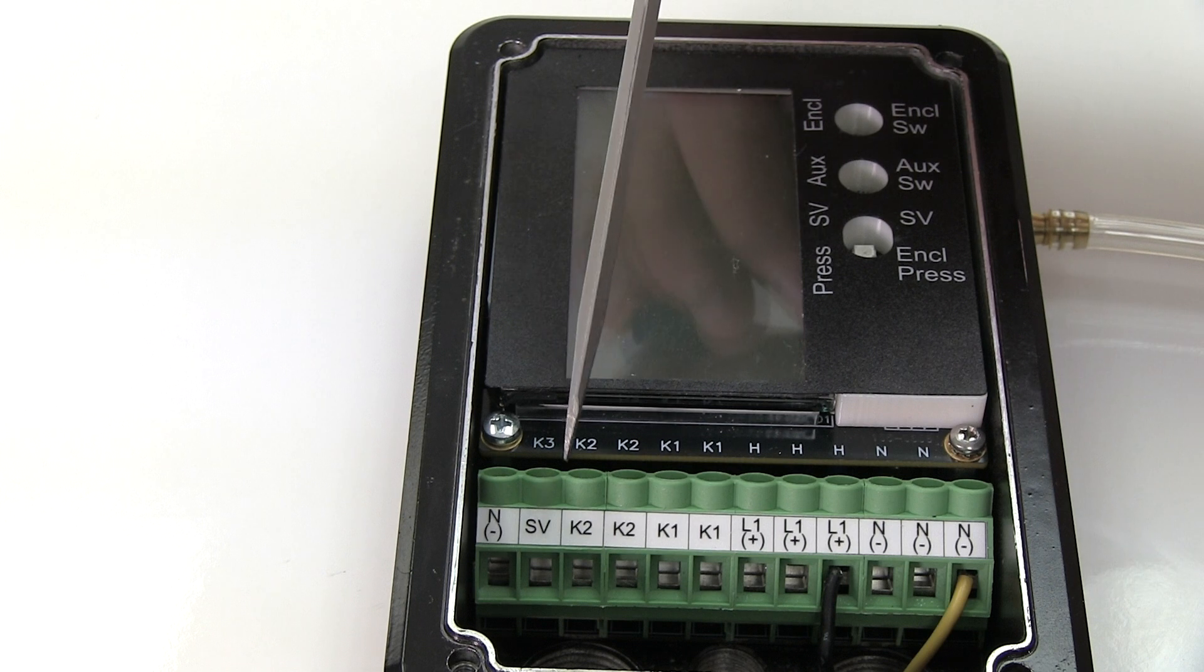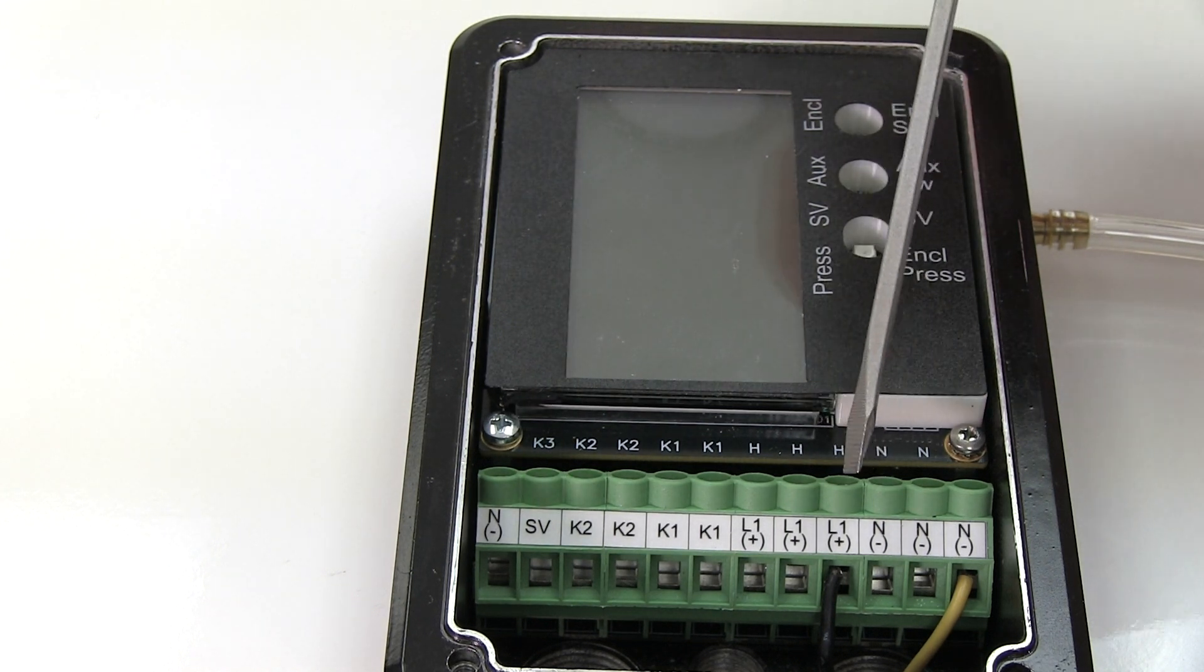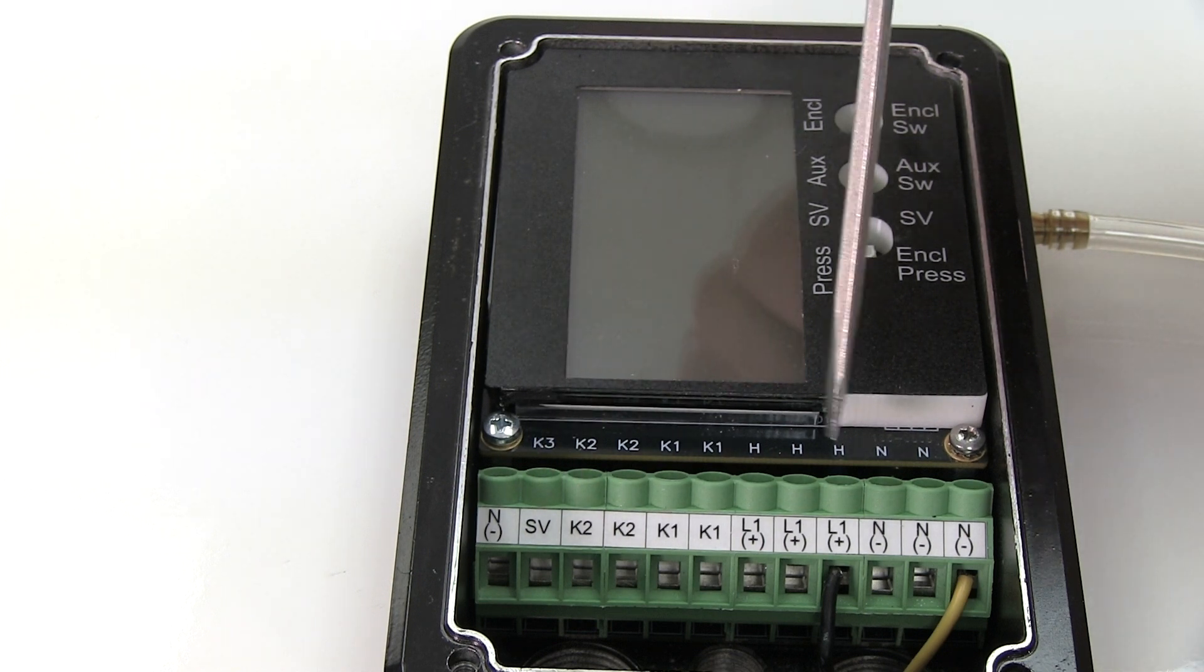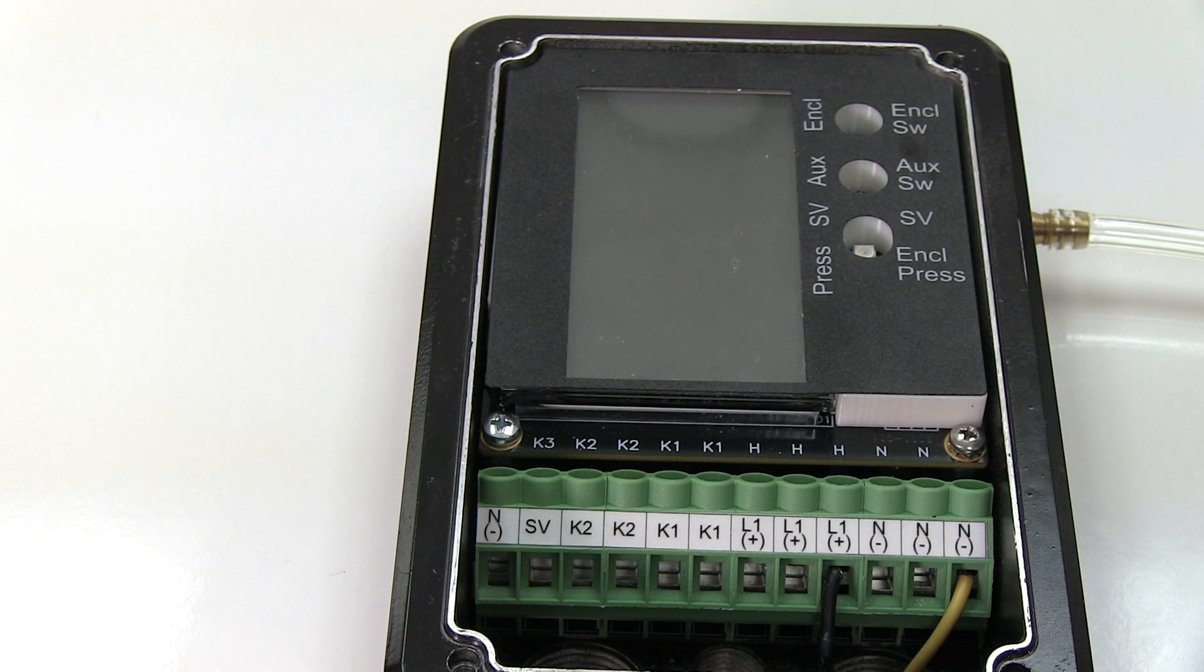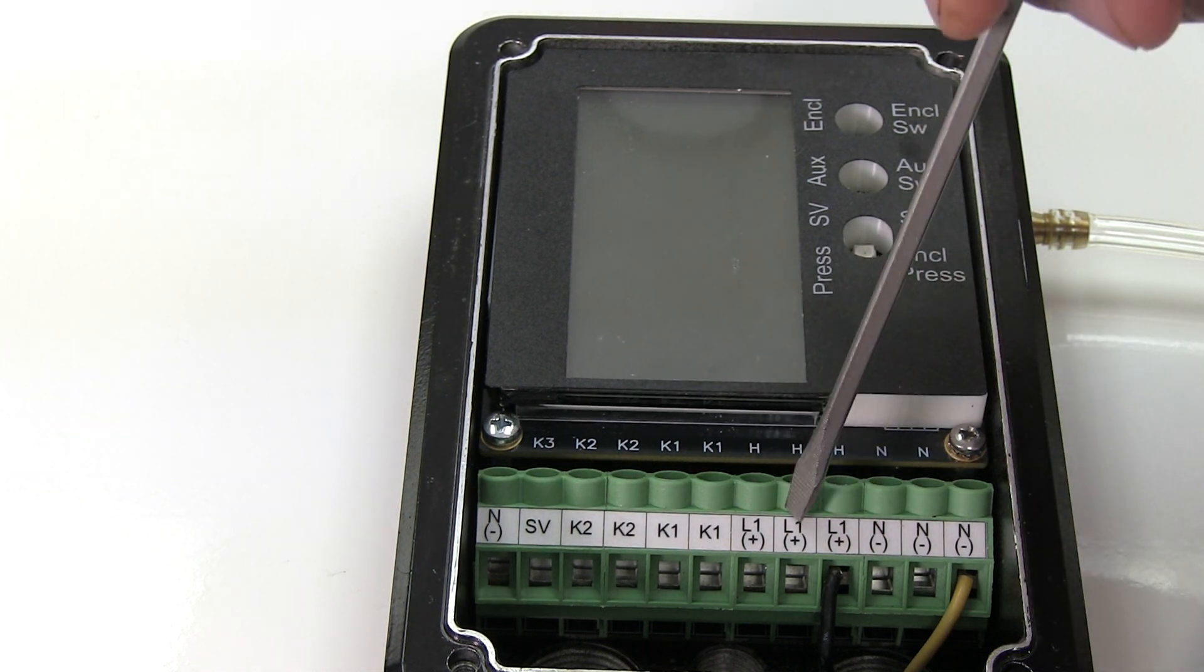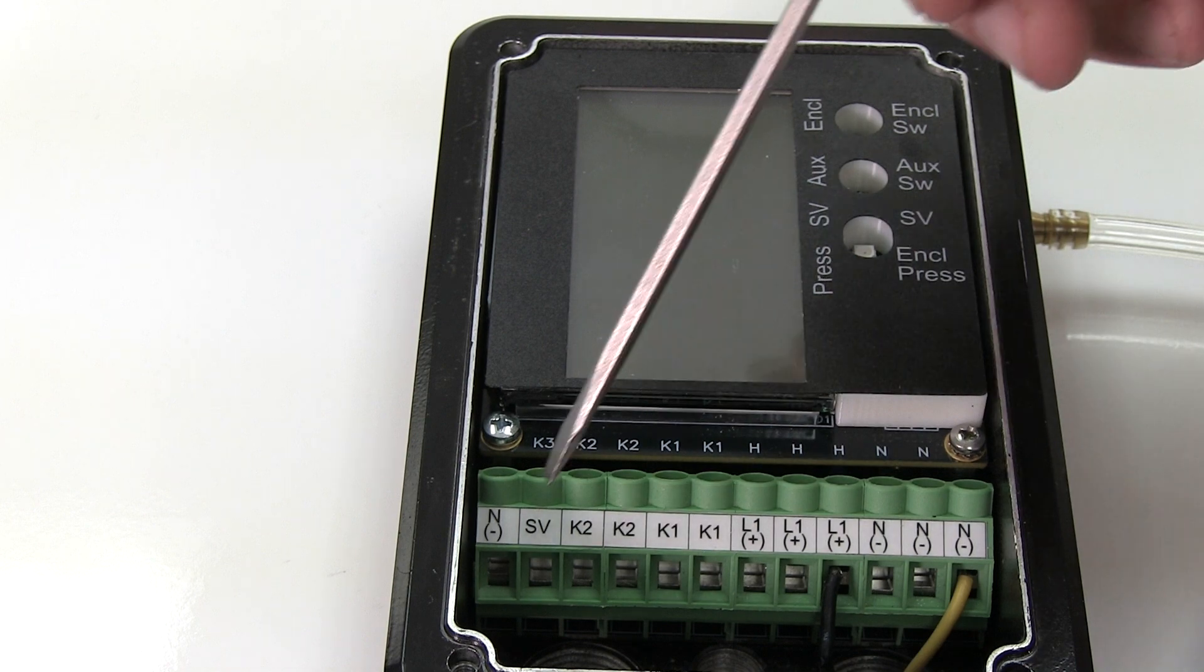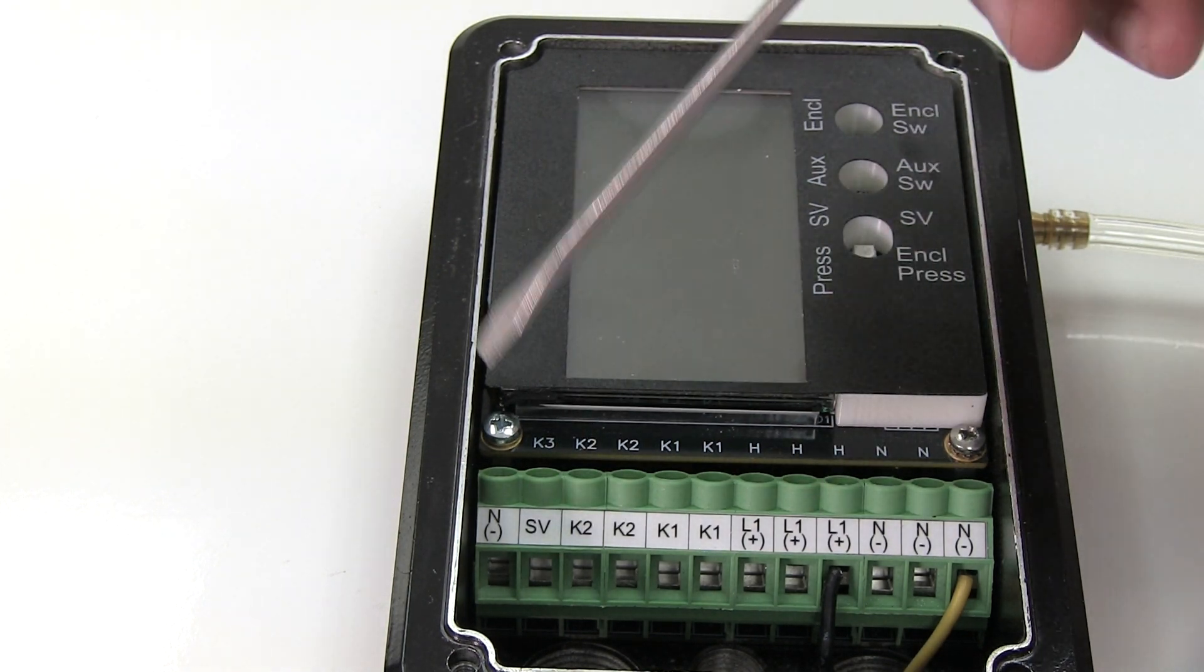All of the L terminals and the SV terminal are connected via bus. So now all three are hot. The SV has an internal contact. So if the solenoid valve is supposed to energize, it'll close and it's connected to our hot bus. So it will be energized. All of the L's and the SV are on one bus and it's all hot.